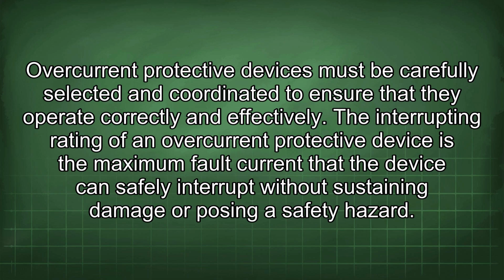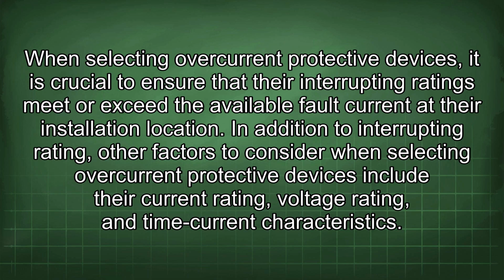The interrupting rating of an overcurrent protective device is the maximum fault current that the device can safely interrupt without sustaining damage or posing a safety hazard. When selecting overcurrent protective devices, it is crucial to ensure that their interrupting ratings meet or exceed the available fault current at their installation location.